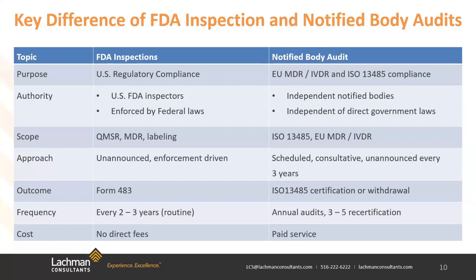If we look at the scope, FDA inspections focus on compliance with FDA regulation, including QMSR, labeling, reporting, and product-specific requirements, which includes pre-market, post-market, and follow-up or for-cause inspections because of a recall a company may have had or an adverse event that they've been made aware of. Whereas the notified body audit primarily assesses compliance with ISO 13485 and the EU MDR, IVDR, focusing on the entire product life cycle, which includes design dossier reviews, technical document checks, and clinical evaluation requirements.